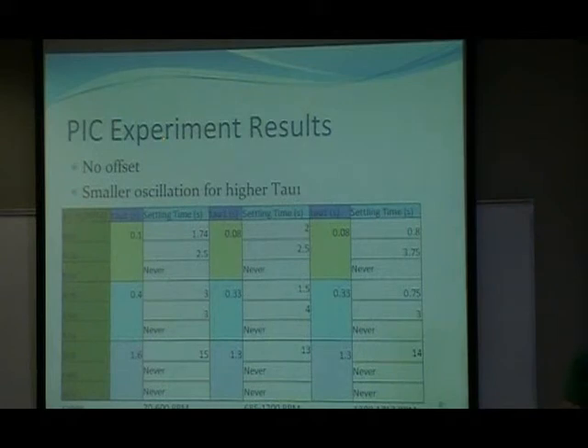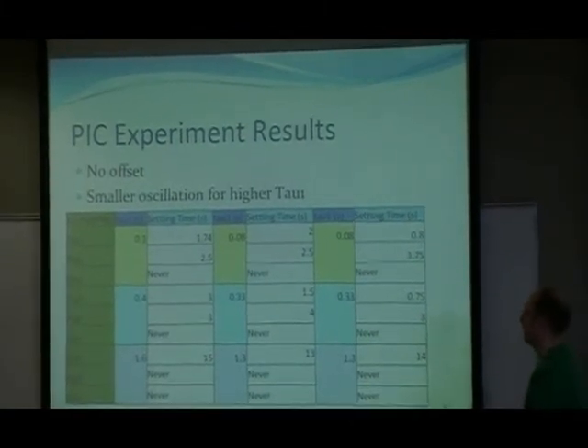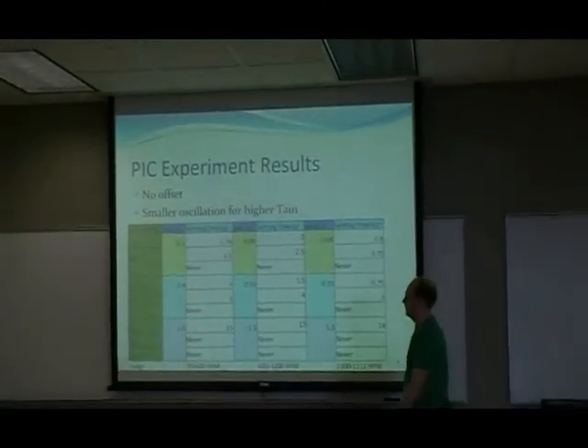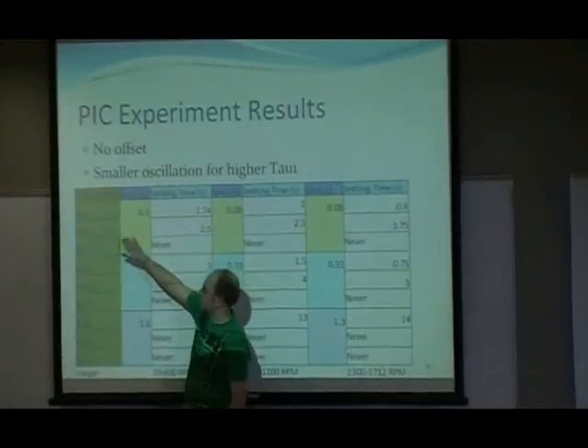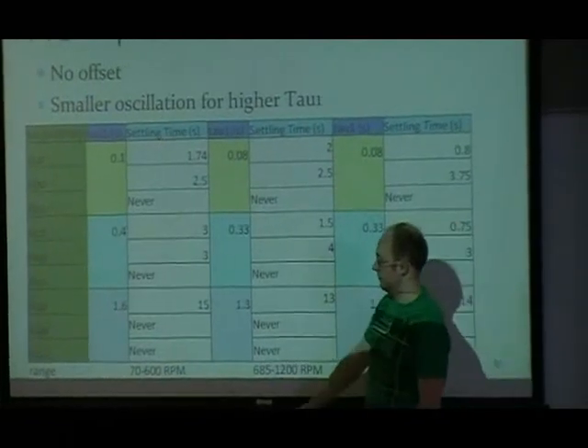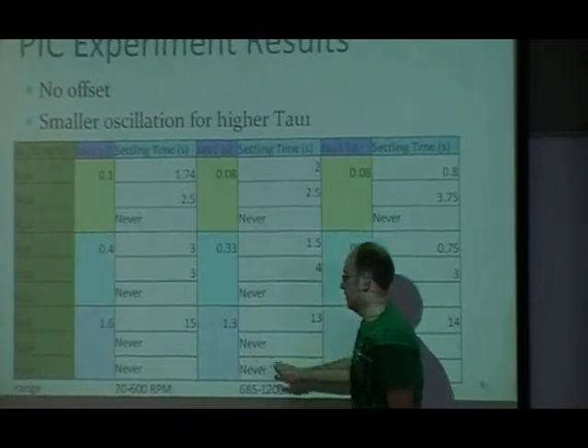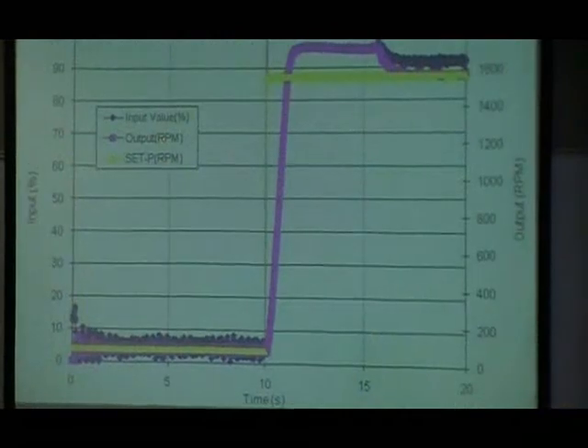These are the PI experiment results. Because it's a proportional integral controller, there is no offset, and there is a smaller oscillation for a higher value of tau1. You can see the settling time for each value of tau1 with each value of KC for each range. With higher values of tau1, the oscillation becomes more prominent the higher the KC value.